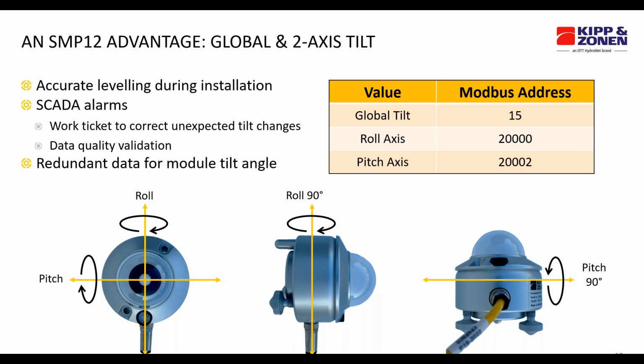The SCADA software can use that data to set alarms for unexpected changes in sensor orientation, whether that's a stationary level GHI sensor or a POA sensor on a tracker that has a repeated pattern every day as it rotates east to west.